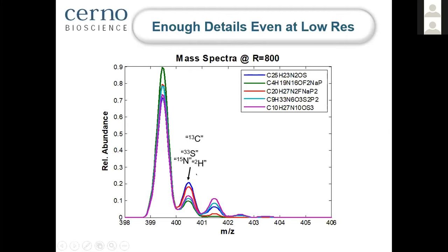Now, at such a resolving power, you cannot tell the difference between the various higher isotopes, whether the plus one, for example, is being contributed by nitrogen 15, sulfur 33, carbon 13, or hydrogen 2. However, the mass spec, especially a well-engineered mass spec, can faithfully combine the various higher isotopes and give you an overall profile that's truly representative of the particular combination of the atoms and elements and their higher isotopes. Thereby, they reveal the possible elemental composition. So that gives us confidence that it might be possible to determine elemental composition using even a quadrupole system, as long as we keep the raw profile data acquired, saved and analyzed in the profile mode without the centroiding process.